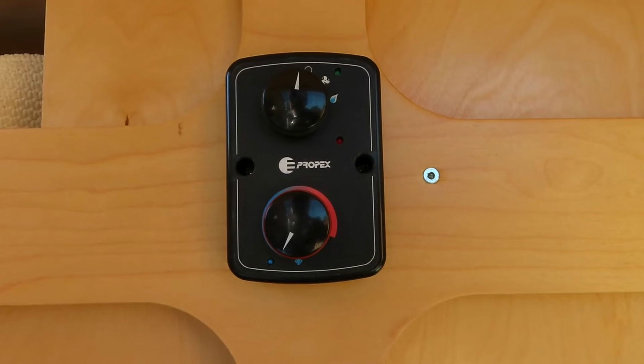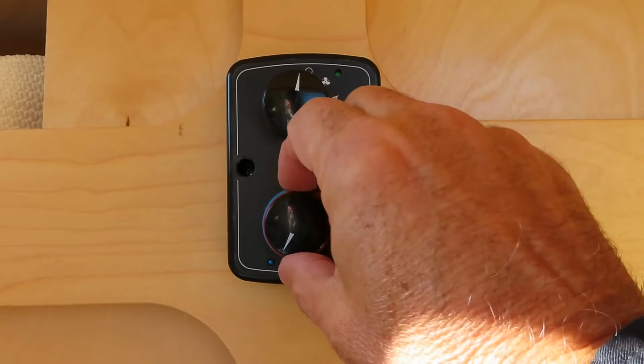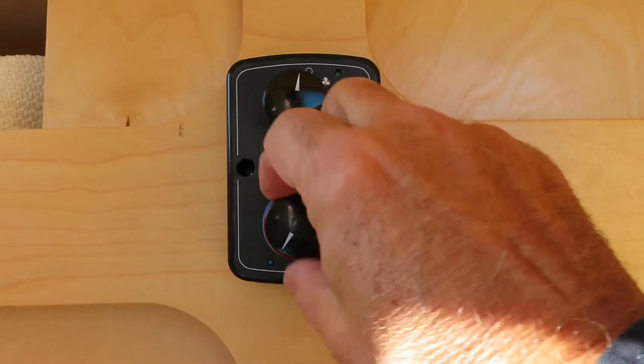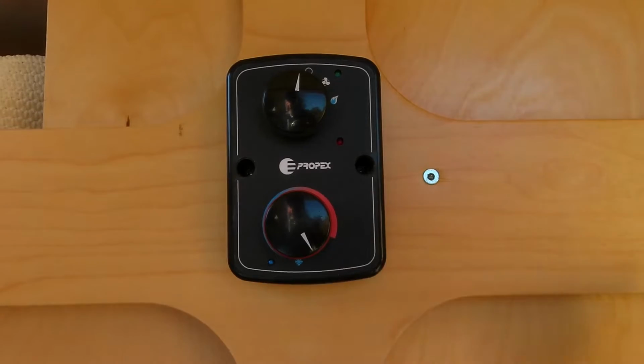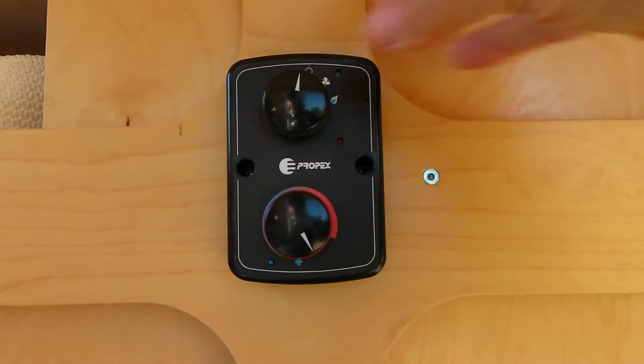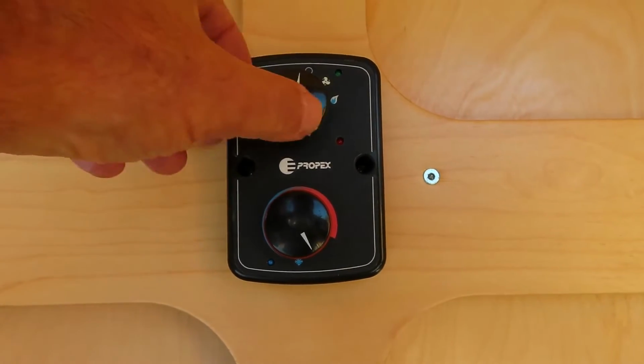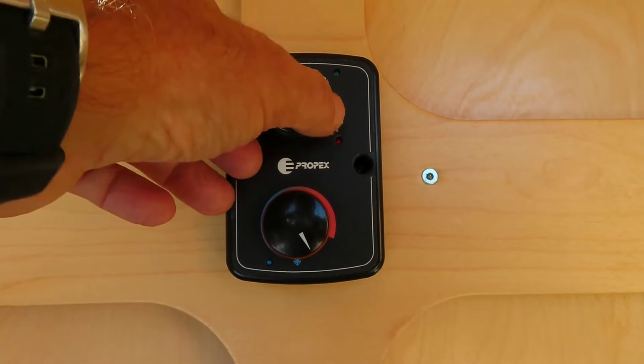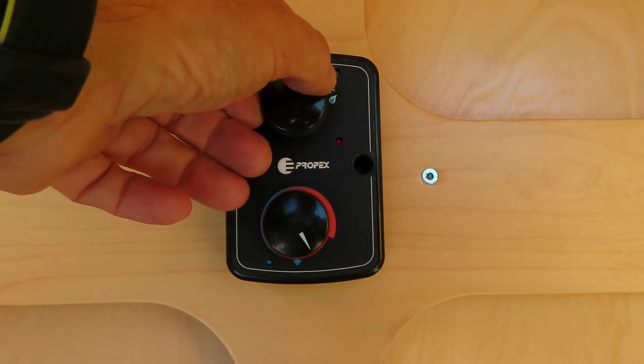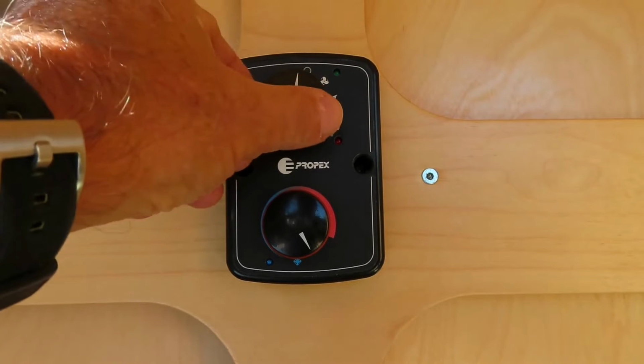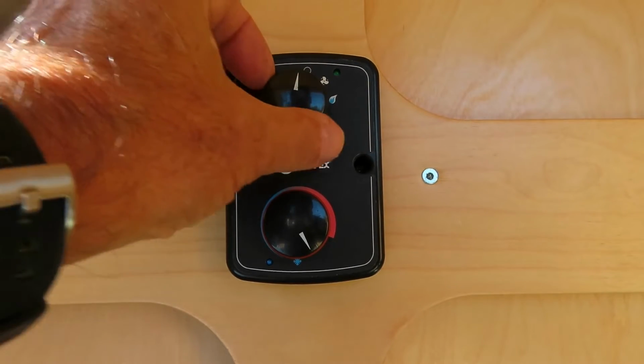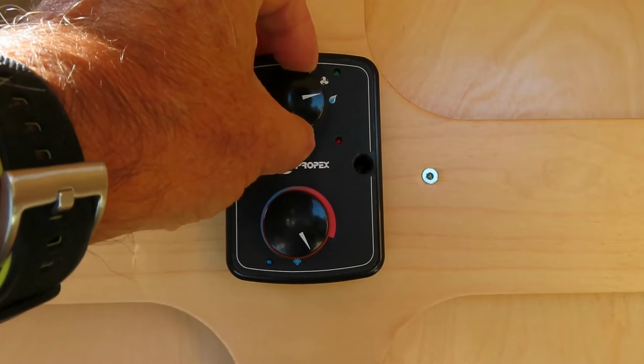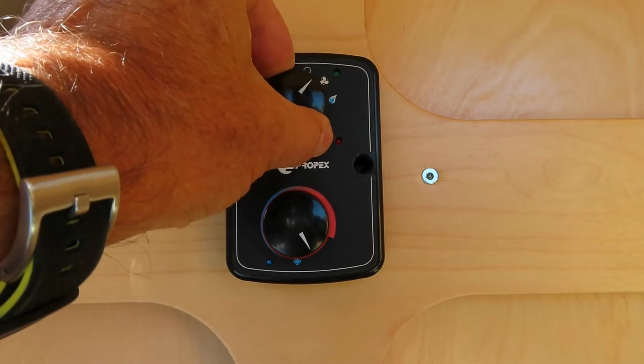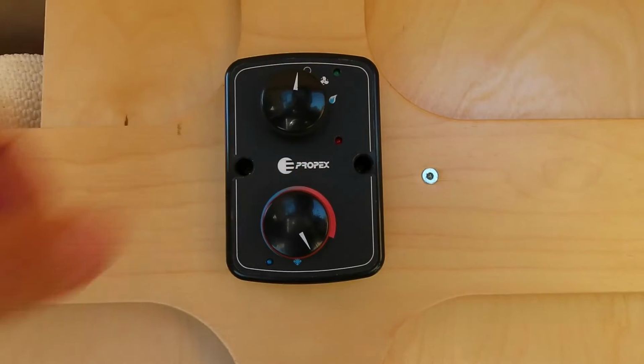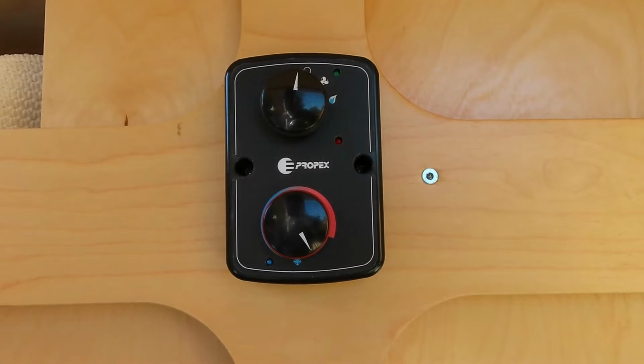Often a code can be cleared very easily just by using the thermostat. To do that, you turn the temperature all the way to high, and you turn the on-off switch to fan heat, fan off, fan heat, fan off. I'll do it now - you want to do this in just under a second each click. That's often enough to clear most error codes.